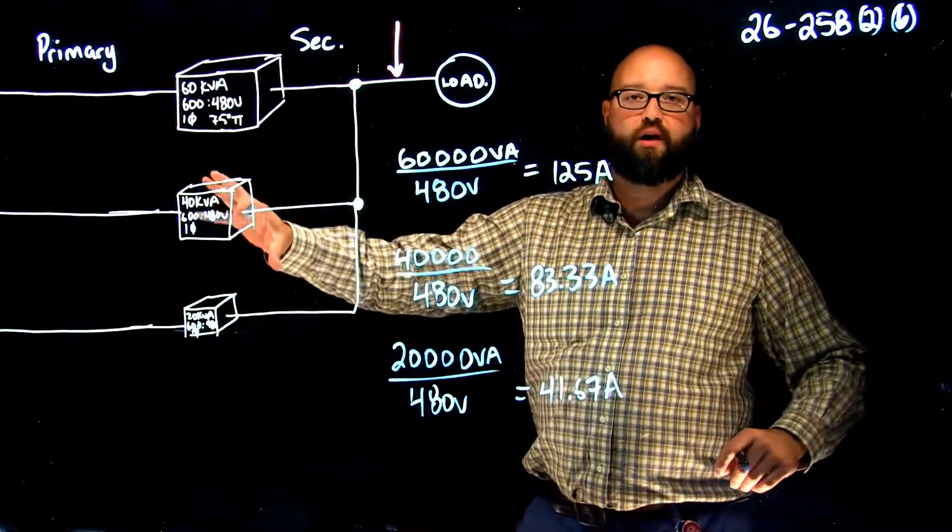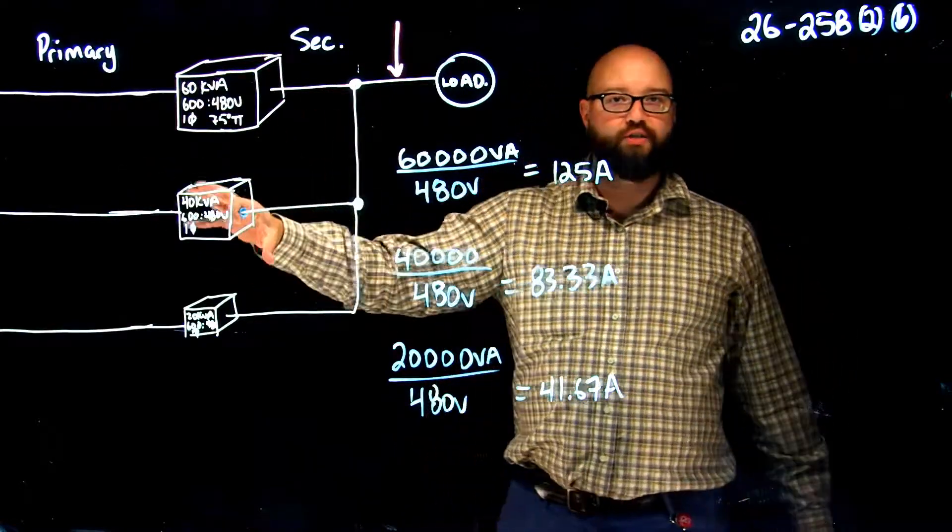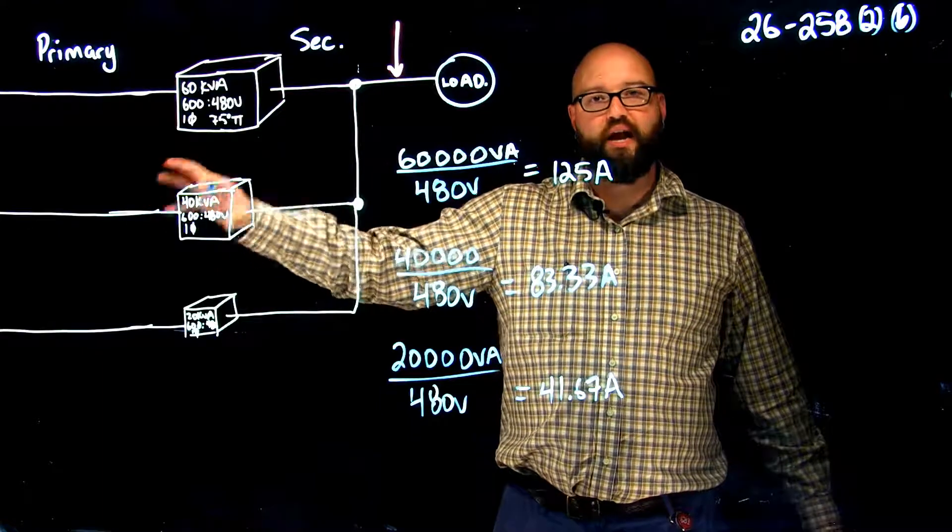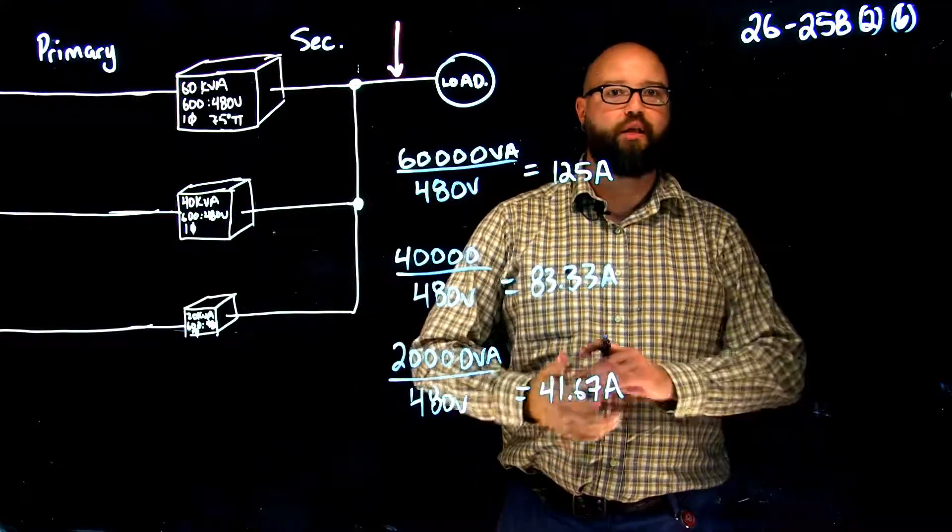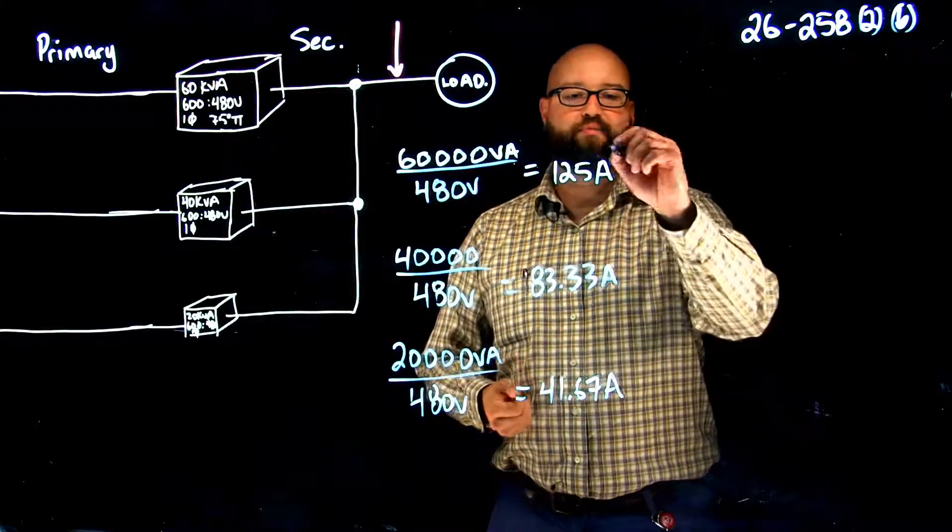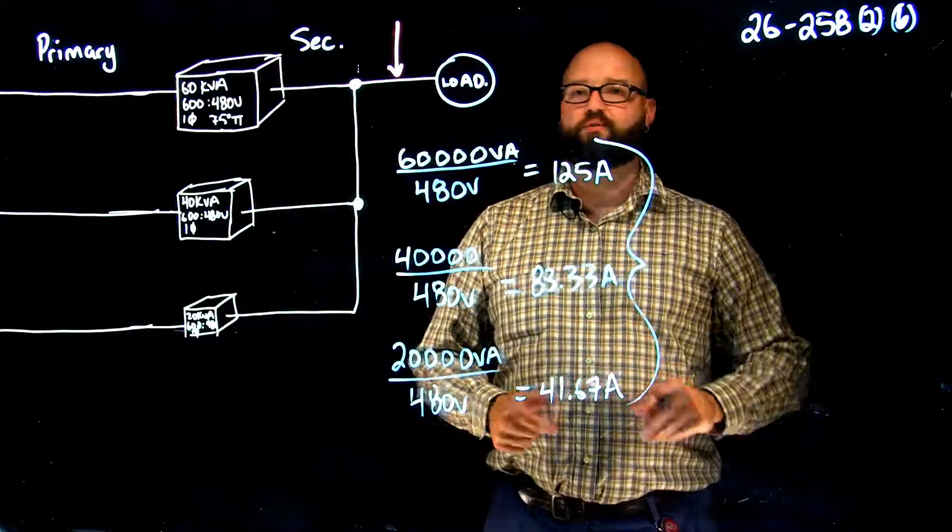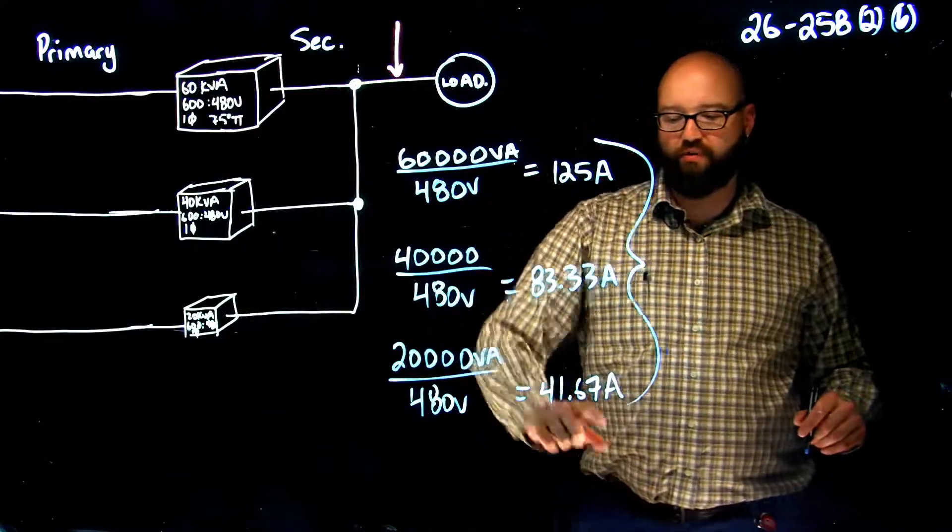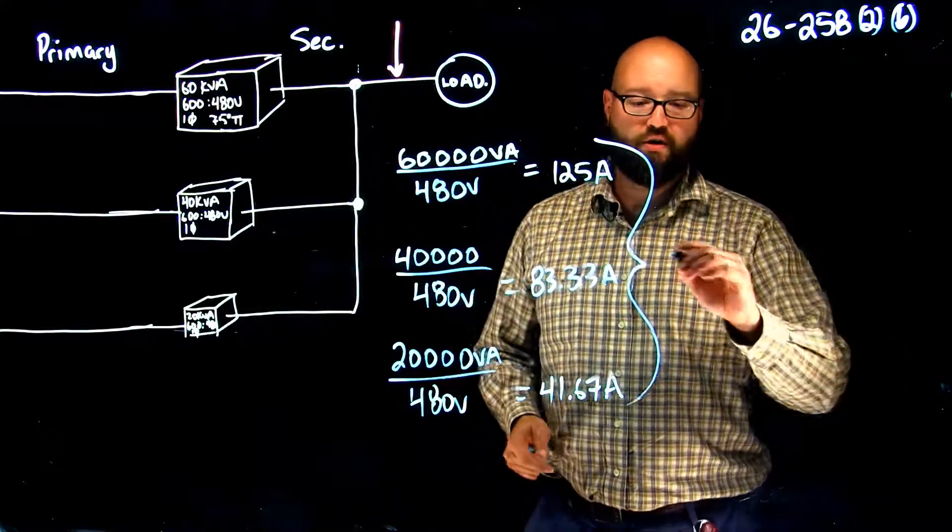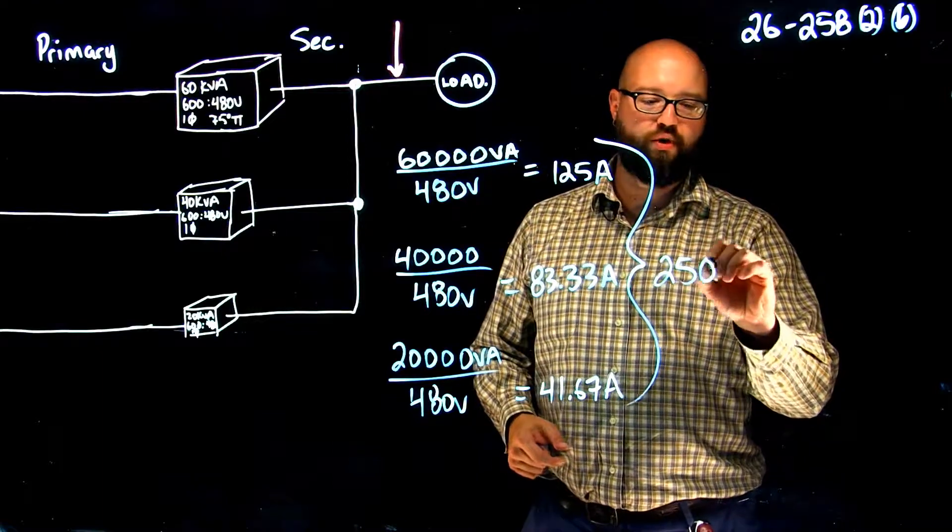Now on the primary side when we had a parallel we took the largest at 125% and added the rest, this is where the difference is when we move to the secondary parallel connection. We are going to take the total of all of these, we're just going to add them straight up, which if we take 125, 83.33 and 41.67 we should get a nice even 250 amps.